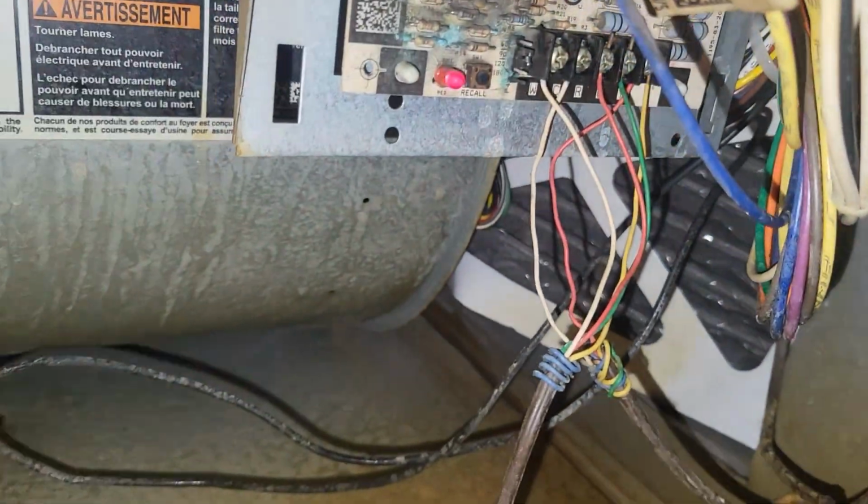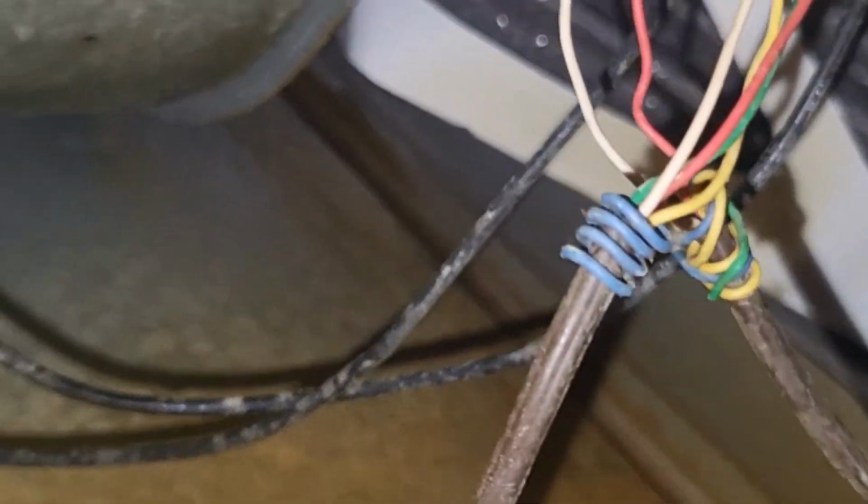Alright, guys. Look at this. If you just press it, you don't have to hold it. If you hold this more than 5 seconds, this is how you erase the last 10 system events. But if you just press it, it should blink fast, and this will let you know what's going on. But I don't have any system events. You see this full heartbeat? That's normal heat operation.